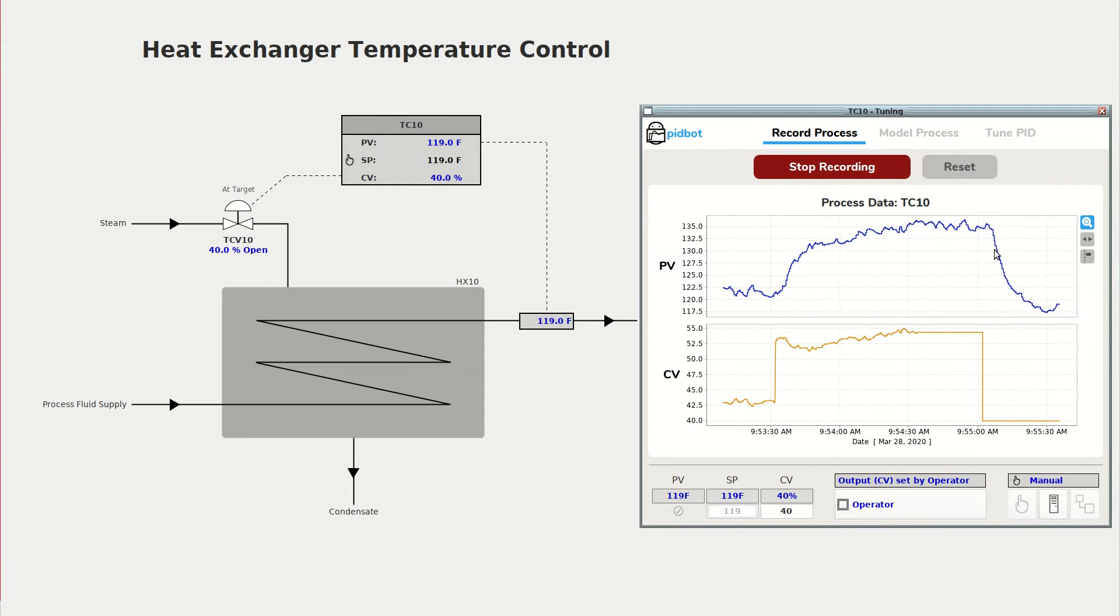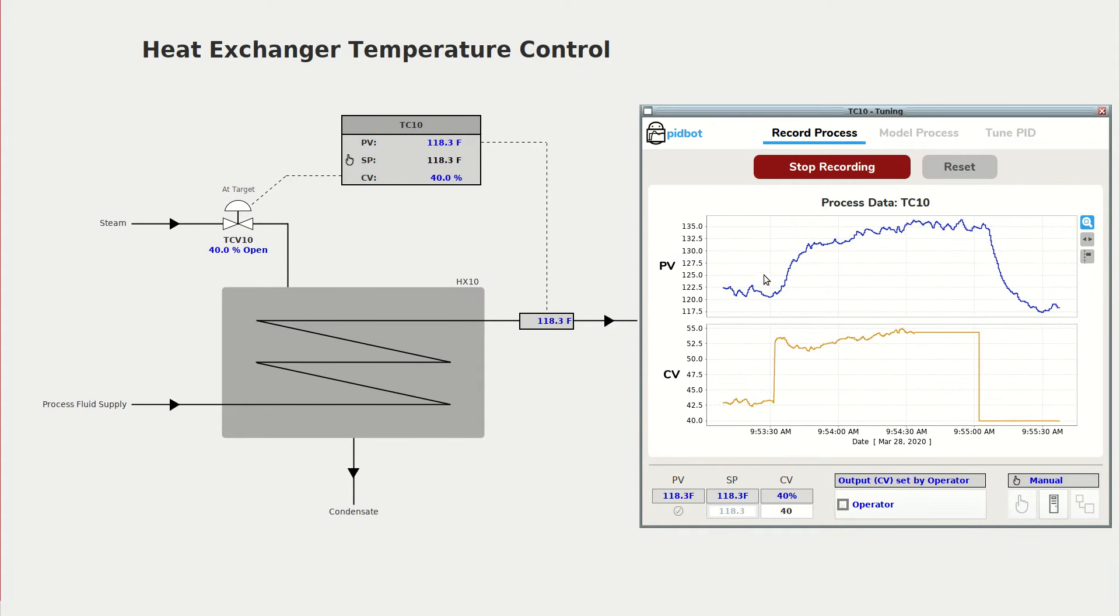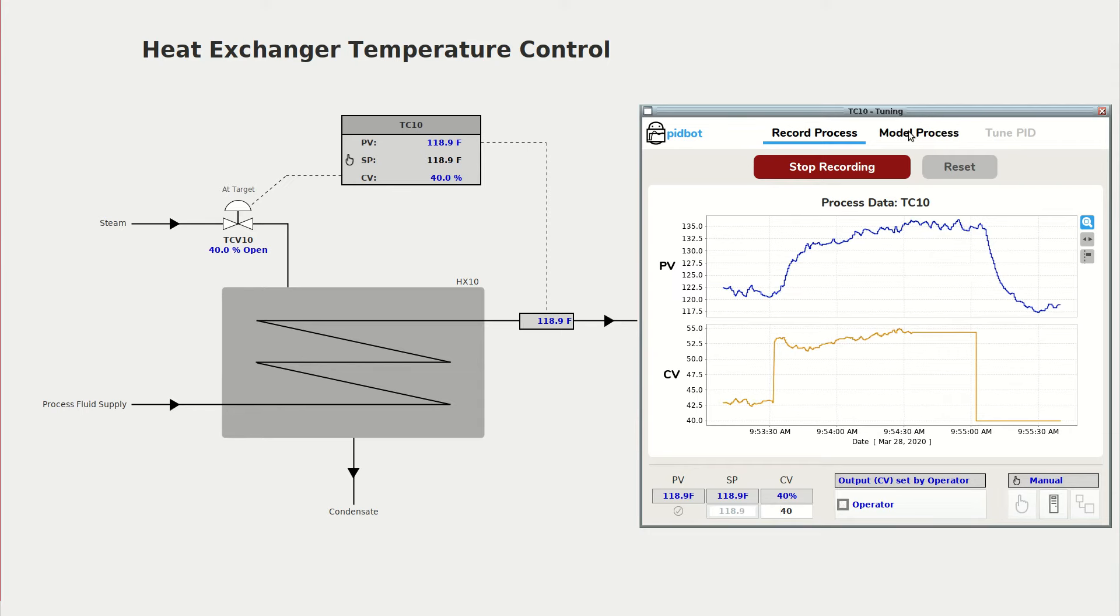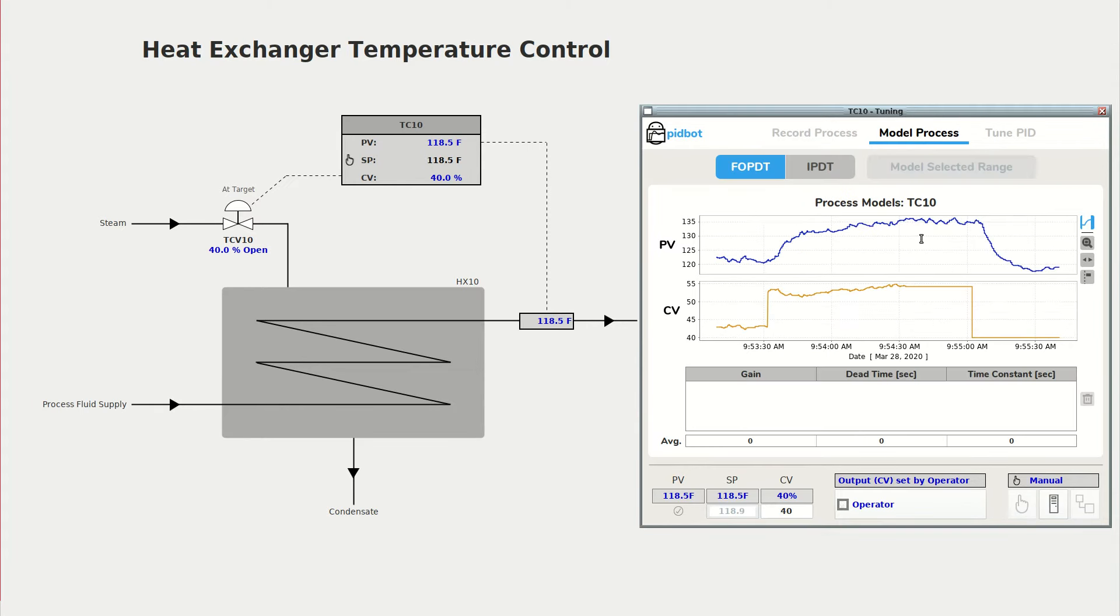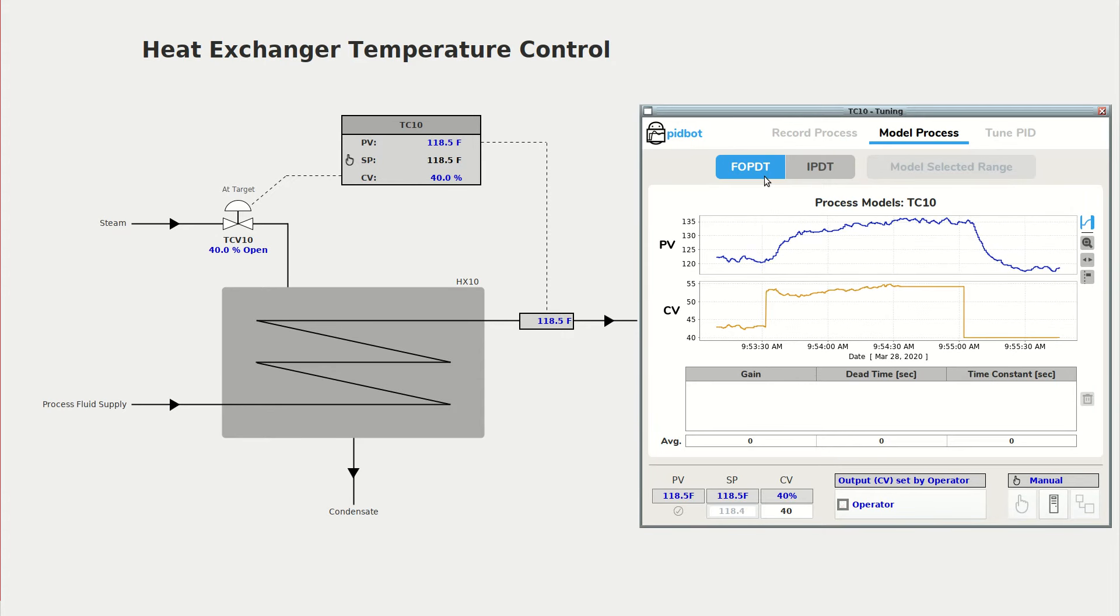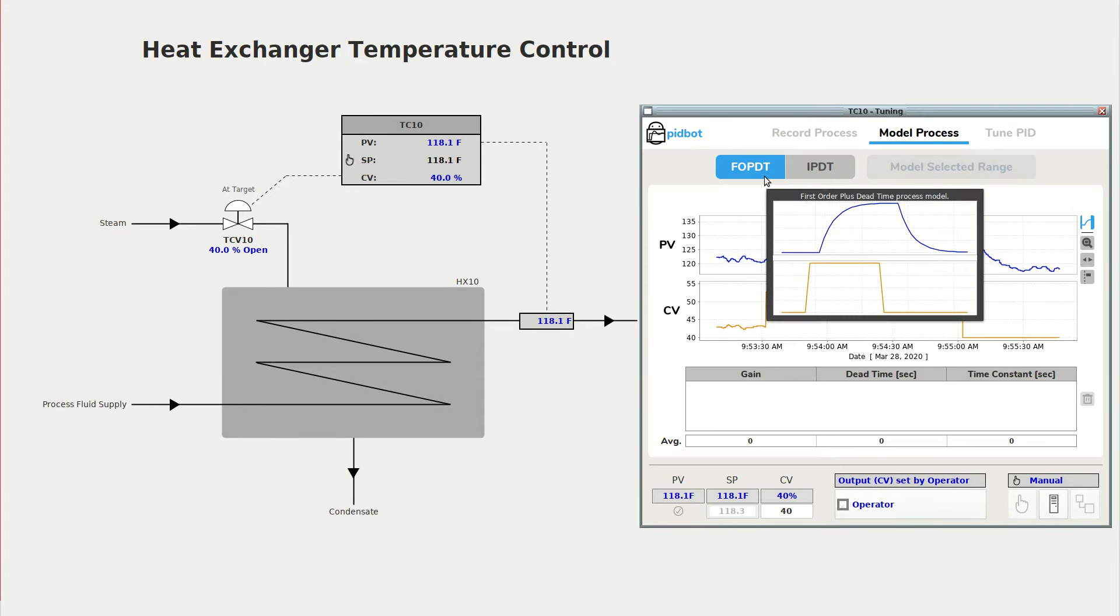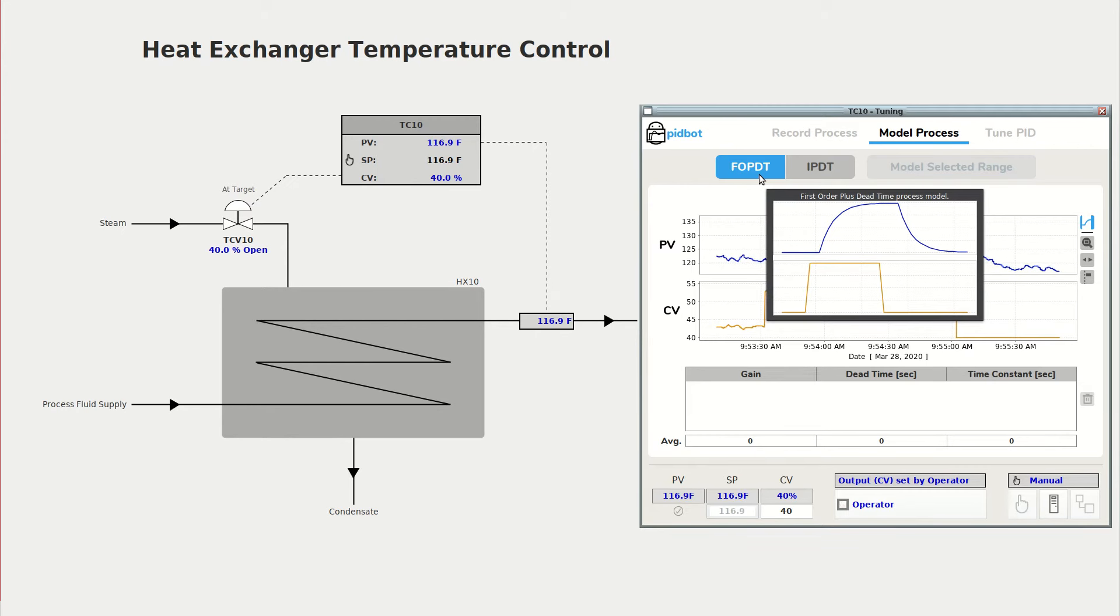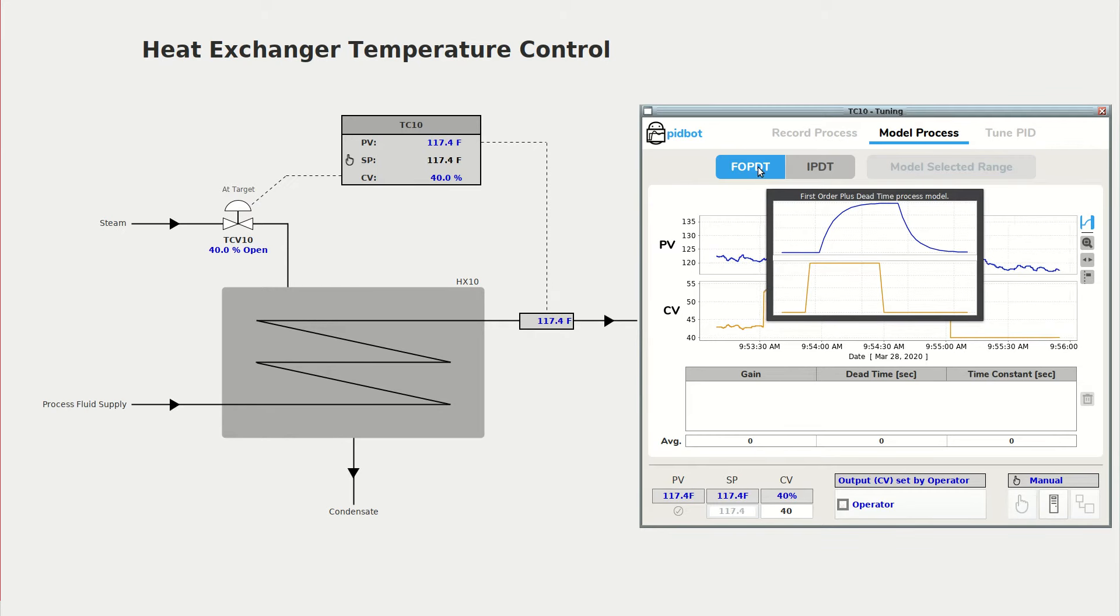And that's good enough for modeling so we'll go ahead and move to the next tab and model our data. So the first thing we do is remember to select the correct model for our process, and for our temperature control loop we almost always want to select the first order plus dead time model.